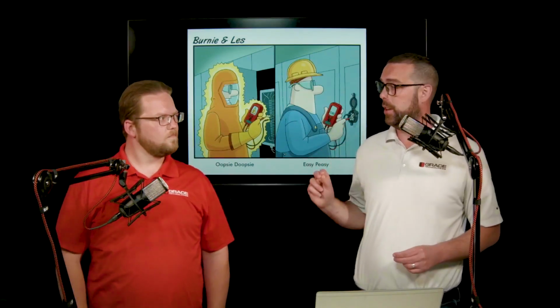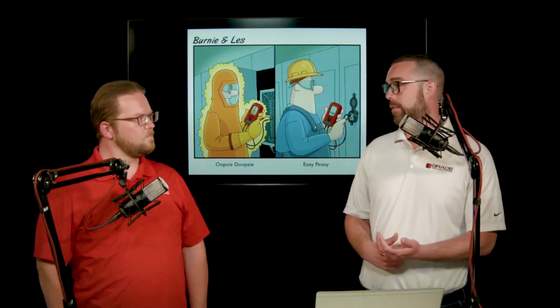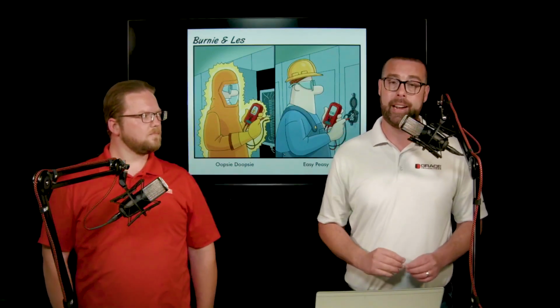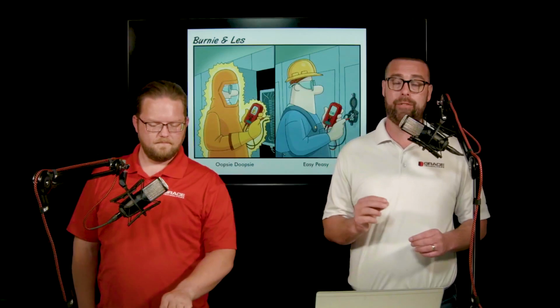On the contact testing side, I want to spend a little time here. That would be our safe test point device, our check volt, our voltage test station. These are all permanently mounted devices installed using a 30 millimeter push button knockout, a small circular hole punch. They come with 4 wire leads ranging from 14 gauge to 18 gauge.